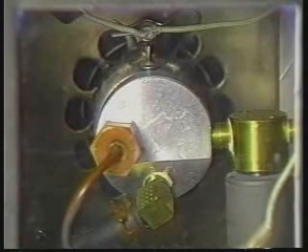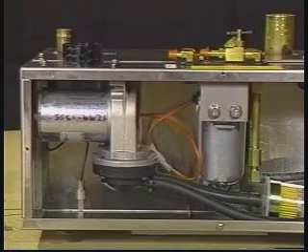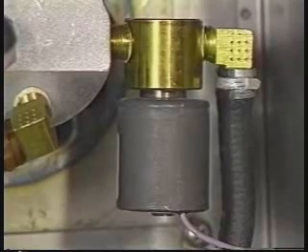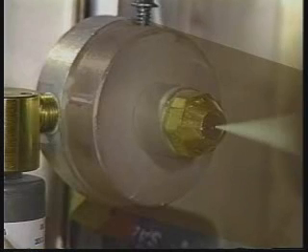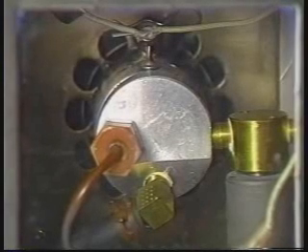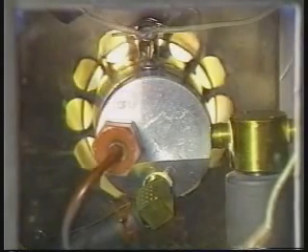The igniter pin glows for 10 seconds, and then the compressor starts, the fuel pump starts, and the fuel solenoid opens. Air is forced out of the fuel nozzle air outlet, creating negative pressure and drawing fuel from the regulator, which exits from the fuel orifice on the nozzle. The fuel-air mixture combines as an extremely fine mist, contacts the igniter, and ignites.